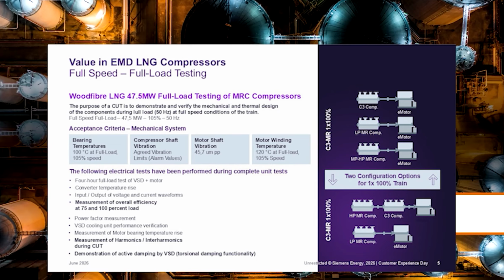So when we did all of our acceptance testing with Woodfibre in Duisburg, we had some different acceptance criteria that lends itself to eLNG compared to gas turbines. So we're definitely testing all of the compressor performance as we normally do in Duisburg, but we're also testing the motor and VFD side of things, because that's where we really want to mitigate risk and give complete assurance for eLNG. So we did a full 4-hour full load VSD and motor test. We had the job transformers, the job variable speed drives, the e-houses, the motors, the compressors.